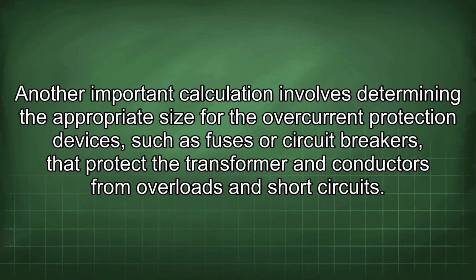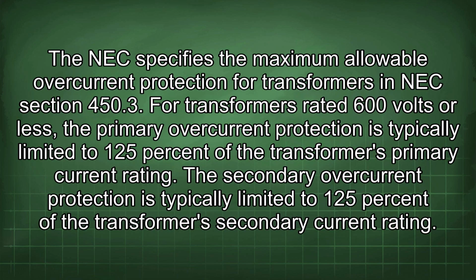Another important calculation involves determining the appropriate size for the overcurrent protection devices, such as fuses or circuit breakers, that protect the transformer and conductors from overloads and short circuits. The NEC specifies the maximum allowable overcurrent protection for transformers in NEC section 450.3.